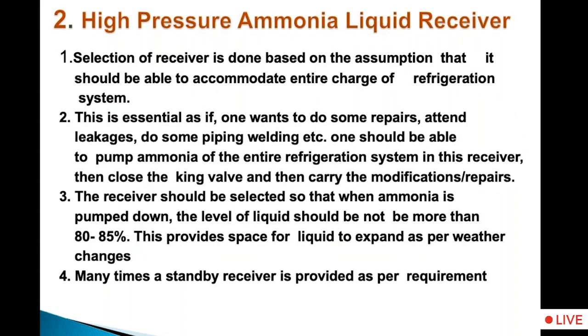So what are the precautions to be taken? Selection should be done on the assumption that it should be able to accommodate the entire charge of the refrigeration system. This is, as I mentioned, so that if somebody wants to do a repair, one should be able to pump down the entire charge. The receiver should be selected at 80 to 85%. Many times a standby receiver is provided as per the requirement, so that you can keep the plant in operation. If it is a critical plant, you cannot stop the plant. So you can pump down the ammonia into the second receiver and continue to use that side when you are attending to one ammonia receiver for thickness measurement, dye penetration test or any other test.